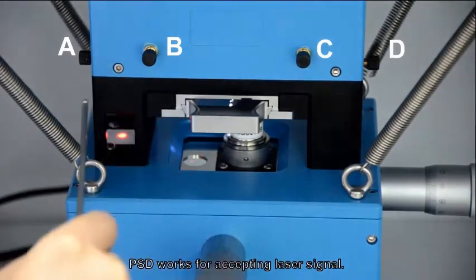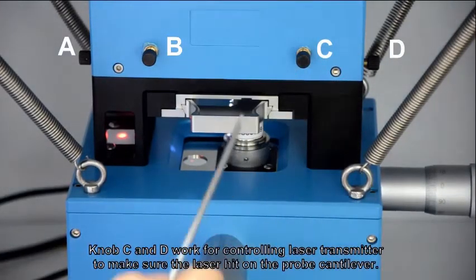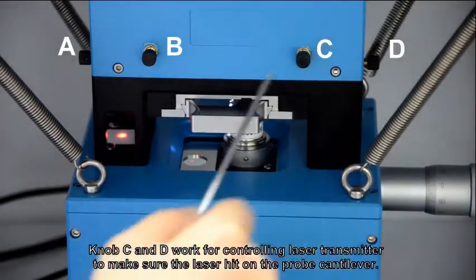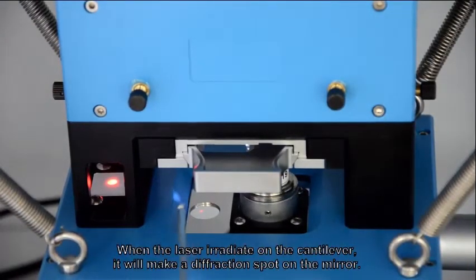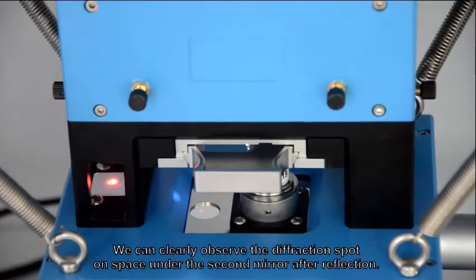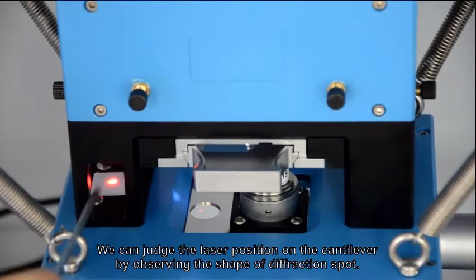Knob A and B work for controlling PSD position. PSD works for accepting laser signal. Knob C and D work for controlling the laser transmitter to make sure that the laser hits on the probe cantilever. When the laser irradiates on the cantilever, it will make a diffraction spot on the mirror. We can clearly observe the diffraction spot on the space under the second mirror after reflection.